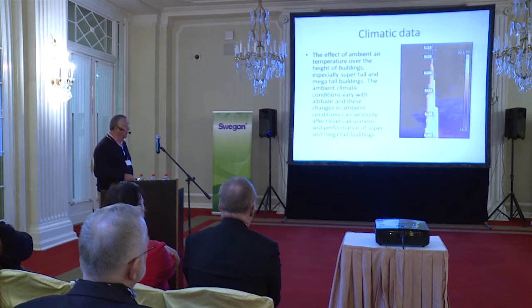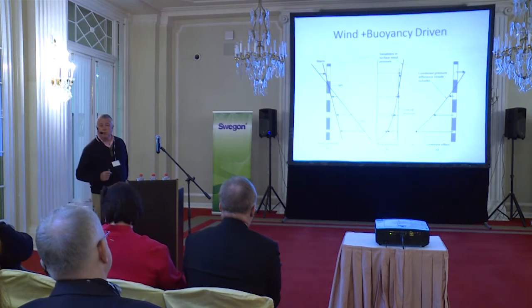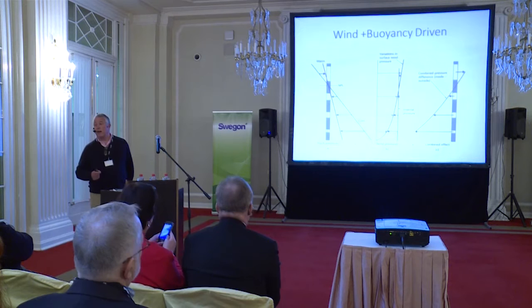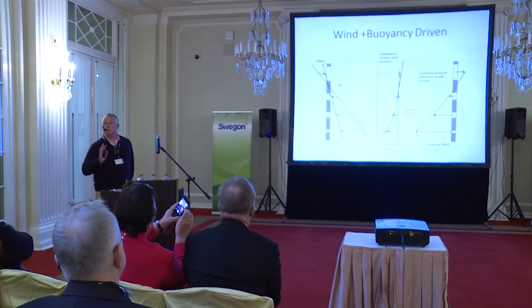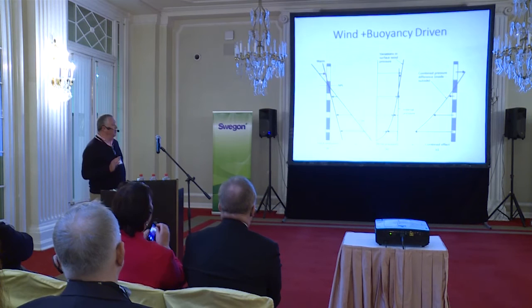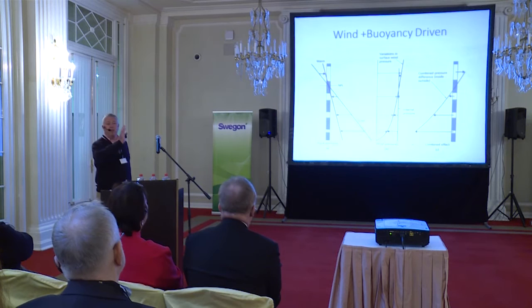I'm not going to spend too much time on this, but when we start doing tall buildings, this is the biggest single element that everybody forgets, called stack effect. Don't quite know how that translates, but you'll find this. It's basically, what is the pressure differential within a building? And the number one person that wants to know about the pressure differential is the fire marshal, the person looking at a fire, because if you have a varying pressure differential in a building, how do you stop the air pressure moving around within there?